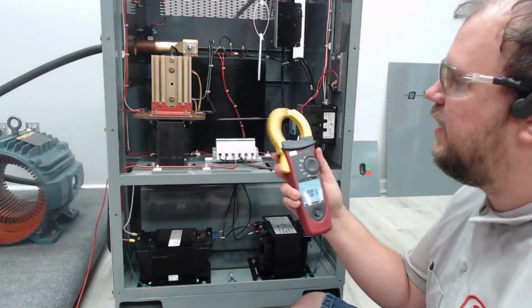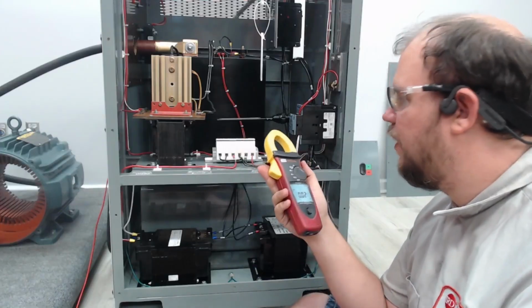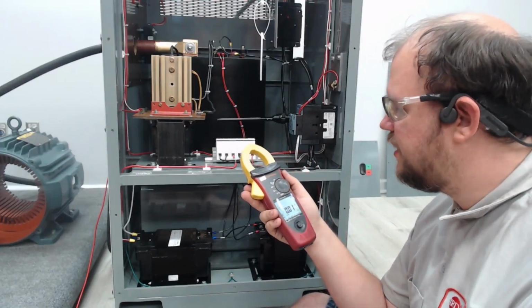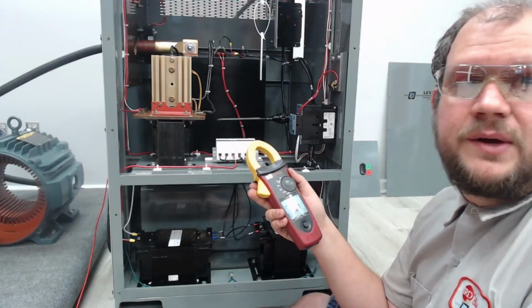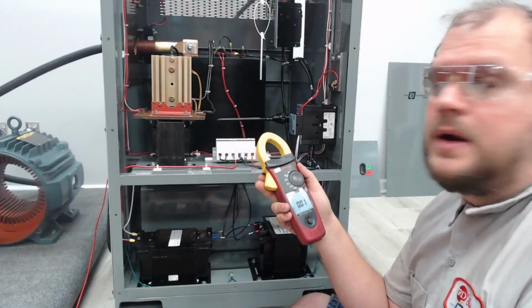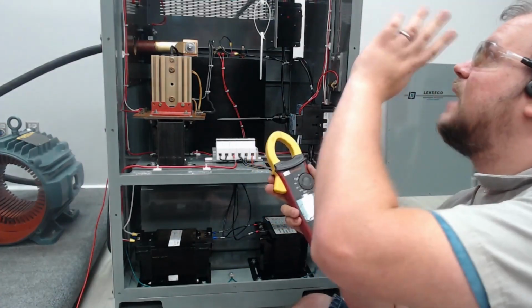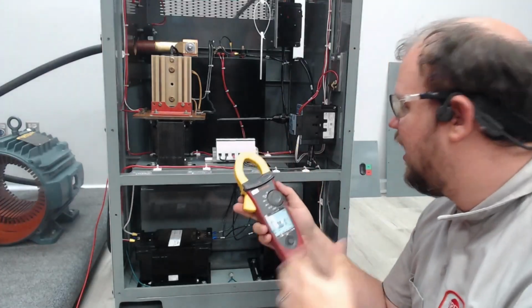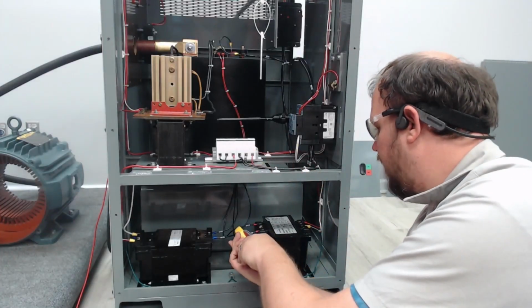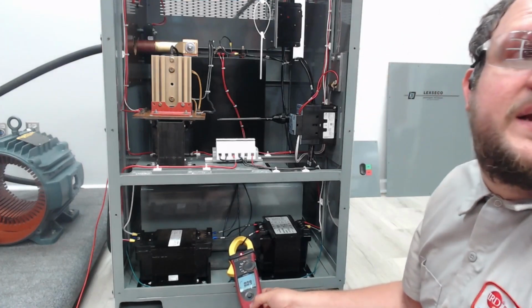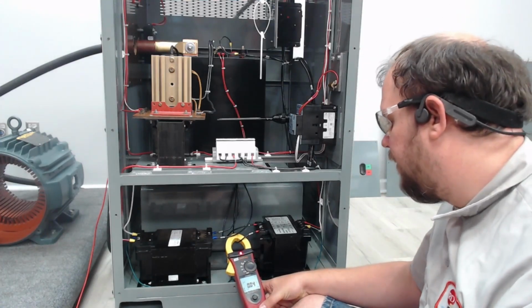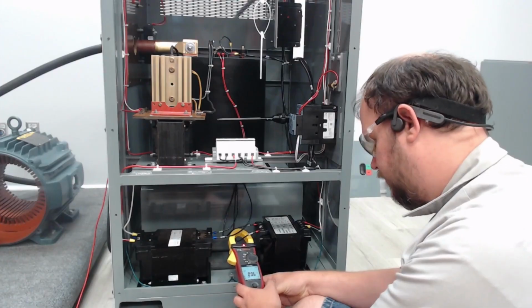Okay, and so I'll have a clamp meter. Makes it easy. You have your own. You might have a fancier one. It doesn't really matter. It just needs to work. We're going to take a reading on the no power. The meter is not yet on, but everything is live. So we're going to take a reading. I may have to talk you through if you cannot see. Yeah, there's some, but basically this is reading 0.06.